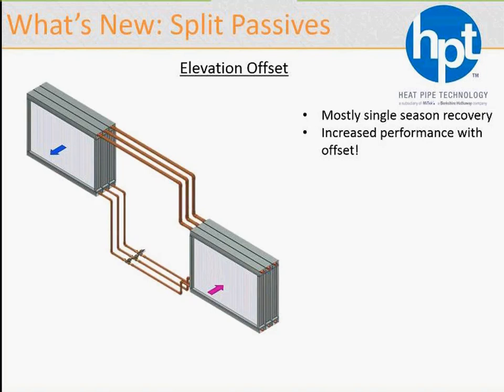How can we improve on this? You probably will guess by now. We include an offset, very similar to the wraparound heat pipe DHPV. The offset is, again, 25% of coil height all the way to 50%, but you start getting really, really good performance at an offset of 25%. Caveat here, this will only work in one season. It'll give you a little bit of performance during the off season, but it'll work in one season. In this particular configuration you're looking at, in winter, the lower side would have to be your exhaust side. During summer recovery, the lower side will be your outside air, and the upper side will be your cooler 70, 75 degree air. With this, much better performance is attained. We'll show you the difference in performance between the offset and without offset.